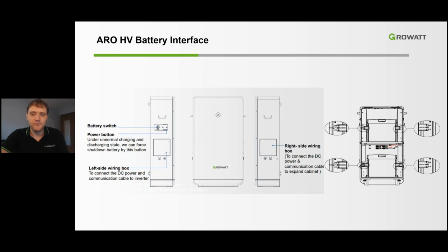Here we can see a little bit about how the interface of the ARO high voltage battery pack is working. The product has a built-in DC disconnect switch to mitigate installation costs and is plug and play ready with the Growatt MIN US inverter. The left side of the wiring box connects the DC power and communication to the inverter, and the right side of the wiring box allows for battery expansion. The picture on the right shows how the battery modules are implemented into the battery cabinet. Up to 3 battery modules may fit inside the ARO high voltage battery. Each battery module features about 3.3 kilowatt hours of capacity. So multiply that by 3, and that's how we get that 9.9 kilowatt hour cabinet.